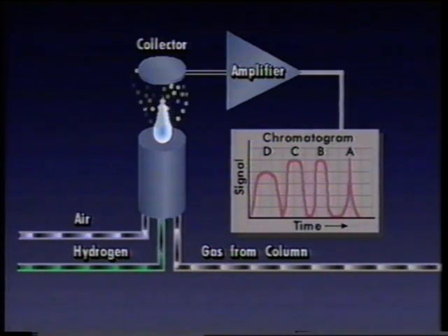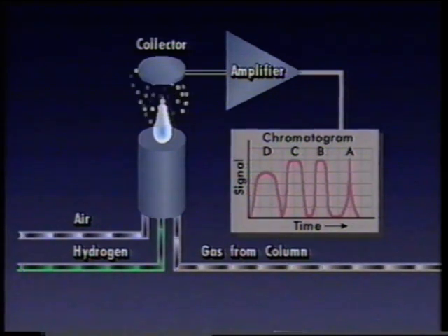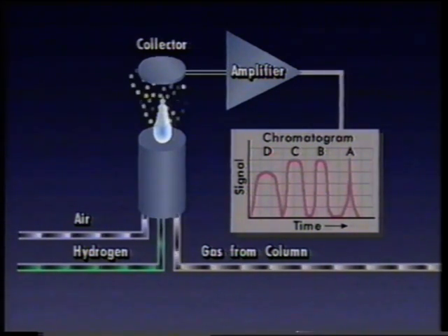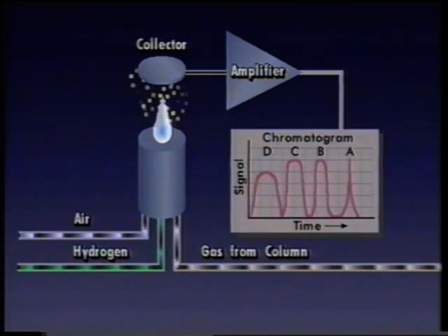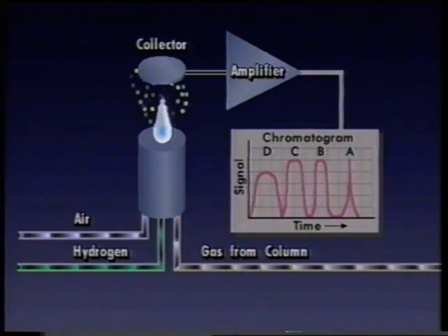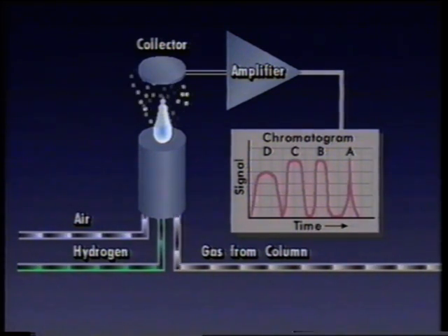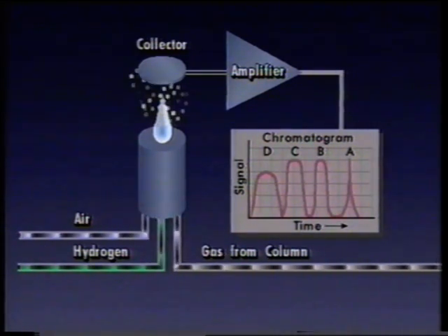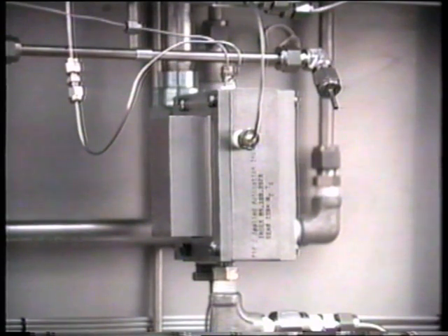The flame ionization detector works on the principle that, when burned, organic matter will produce a number of ions proportional to its carbon number. In this example, a hydrogen flame, fueled by breathing quality air and hydrogen, burns, creating few ions. When sample component A is introduced into the flame, it burns, producing ions proportional to its carbon number. An electrically charged collector attracts the ions and creates a signal that is amplified and sent to the data collection system. The detector's flame burns continuously and is monitored by a thermocouple inside the housing. If the thermocouple senses that the flame has gone out, an auto-ignite sequence will attempt to reignite it. If the flame still does not ignite, an alarm is triggered.